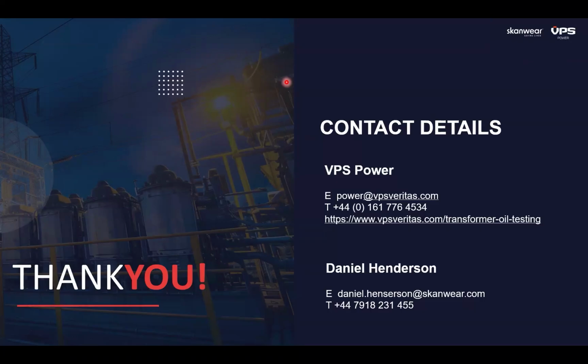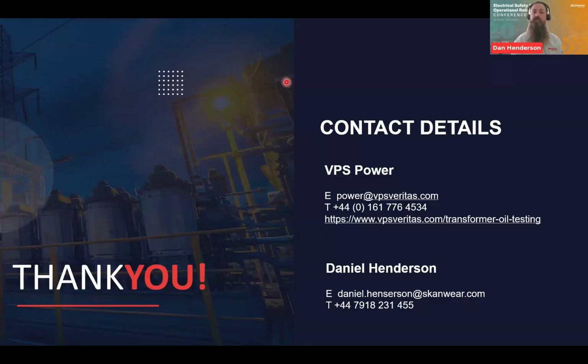Good stuff, thanks, Dan. And Salas also mentioned in chat earlier, online drying of oil is preferred as compared to offline. Again, it's just down to the asset and the protections on it. If it's a standard transformer, that's fine and it's not going to cause any issues. If you've got things like a conservator and a Buchholz relay, there's potential that when you're recirculating the oil, you can get air pockets in the oil, and as they go to the highest point to escape, if they go over that Buchholz relay, the Buchholz will just see it as a pressure, and that can trip the contacts inside the Buchholz relay and trip the asset.